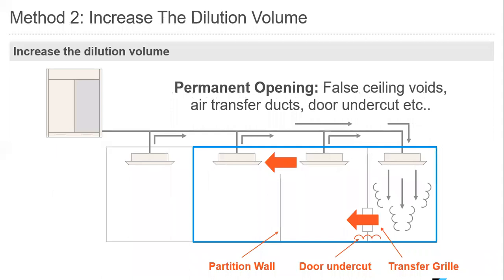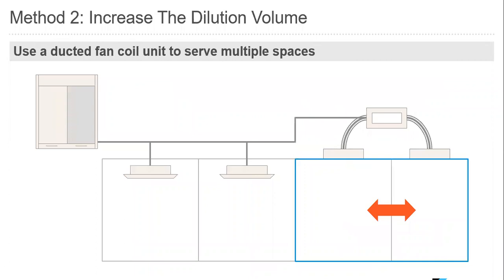So how do we increase the dilution volume? One way is to have door undercuts or a transfer grill. And you can also see here a third way would be to have a partition wall. So 3 different ways. These create permanent openings between spaces and allow us to actually increase the actual volume of the space, which reduces the overall refrigerant concentration limit because we have transfer of air between those spaces. We can also dilute the volume of a space by having a single ducted indoor unit serve 2 spaces that are tied together. And that allows us to serve multiple spaces, actually can help us cut costs in a building, and allows us to further increase that dilution volume.